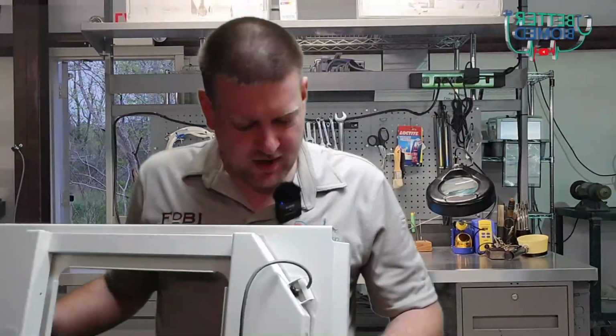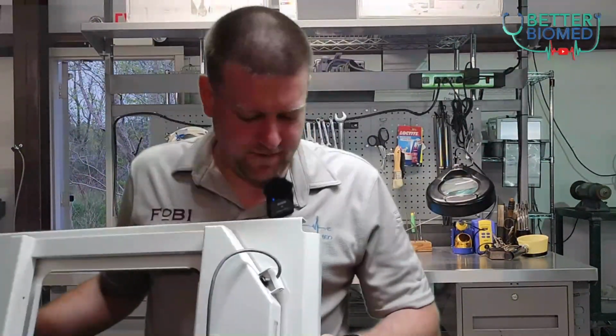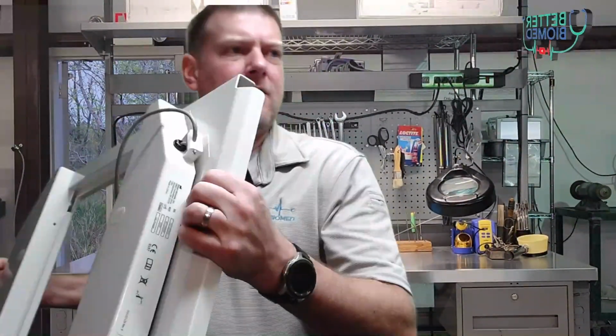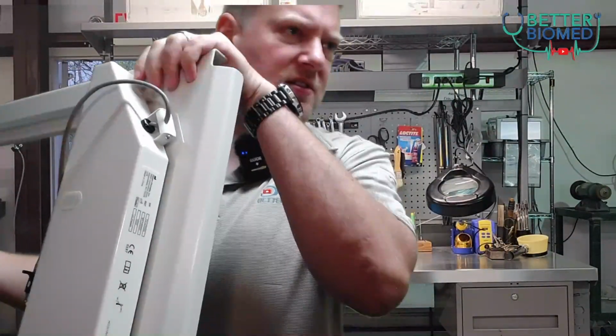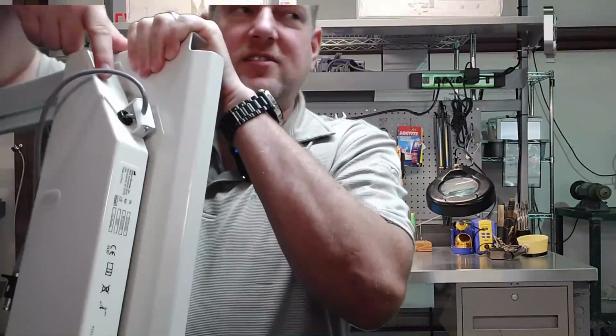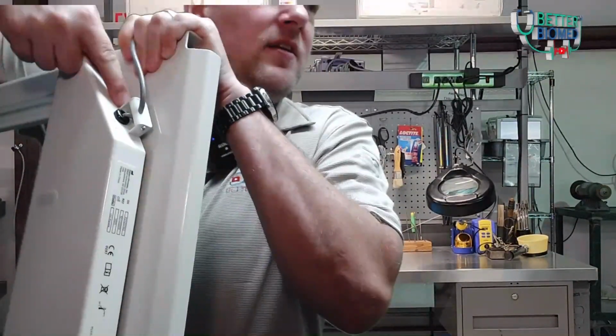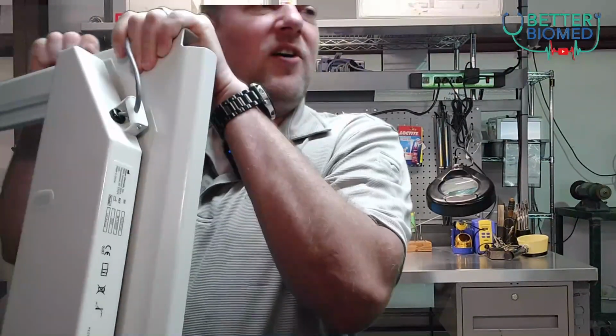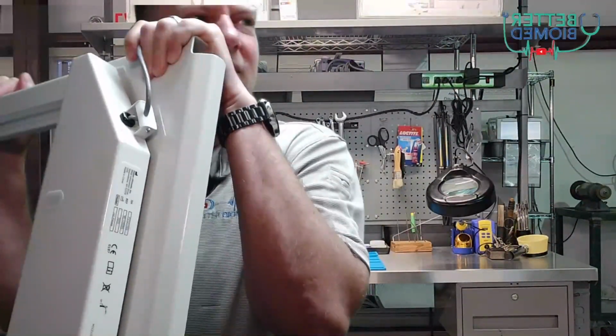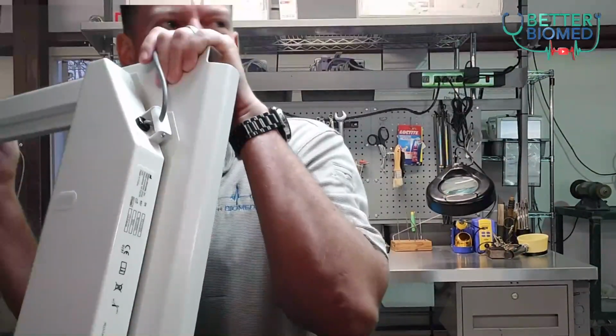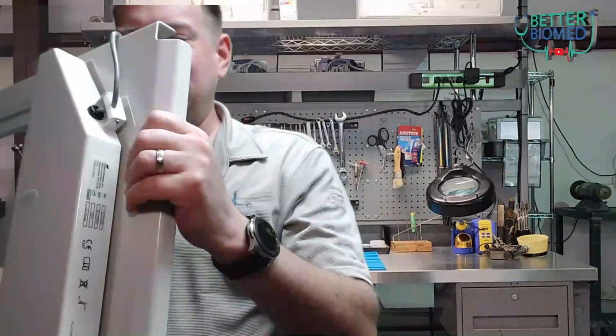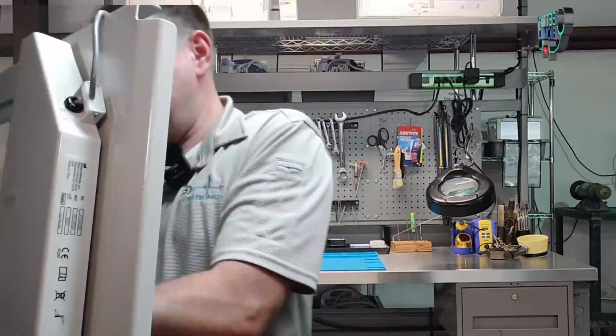So, guys, that's what we're going to do. We're going to take this guy apart, figure out what's going on, and I can maybe see something already. I've got this cord, let's see if I can get you guys a good angle. Look at how this cord is being stressed right here. See that? Look at that crazy angle. It's like they yanked on it and then they tightened it down while it's being yanked. That is not good for the longevity of any cable. That looks like absolute garbage. That's probably not the problem. I'm expecting it to be in the load cells, but we're going to find out together. Coming up next, right here, Better Biomed.